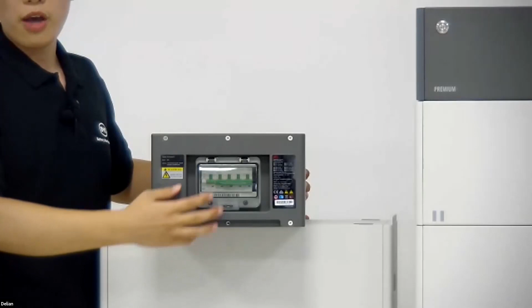To switch on the high voltage batteries, make sure on the right hand side of the BCU we have got the circuit breaker. When you switch on the batteries, please turn on the circuit breaker first to switch on the batteries. If you want to switch off and turn off the batteries, press this button. We have got this button for the premium series, which is also quite exciting. Press the button for 5 seconds to switch off the batteries. So please make sure you follow this sequence and make sure the system is running very well.